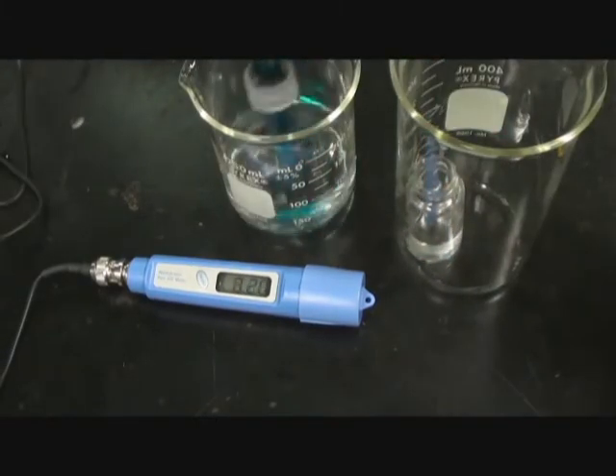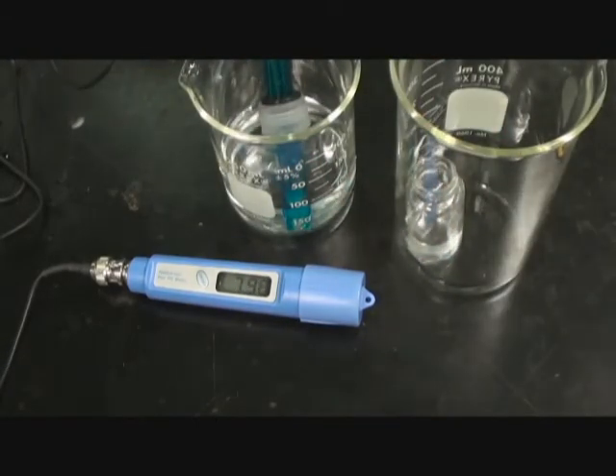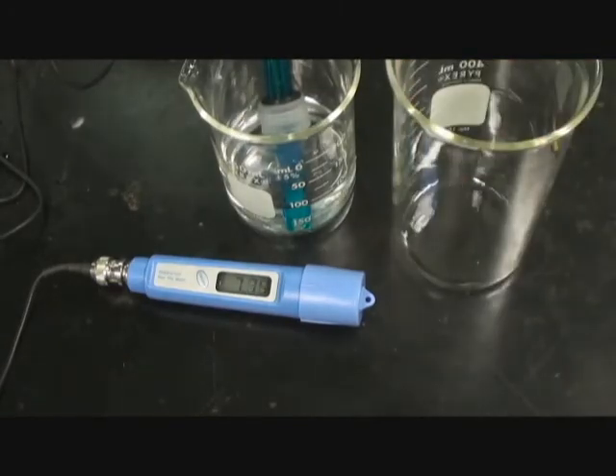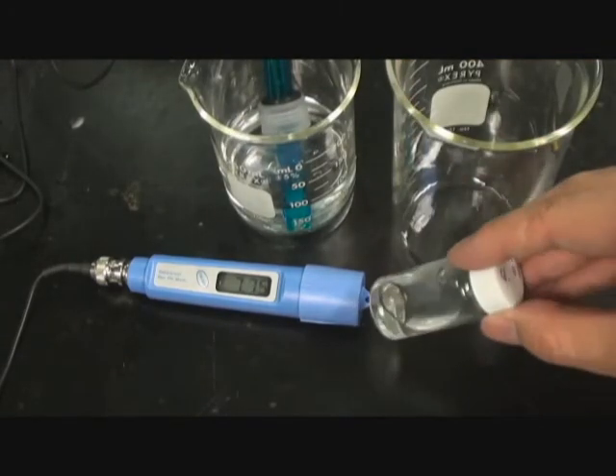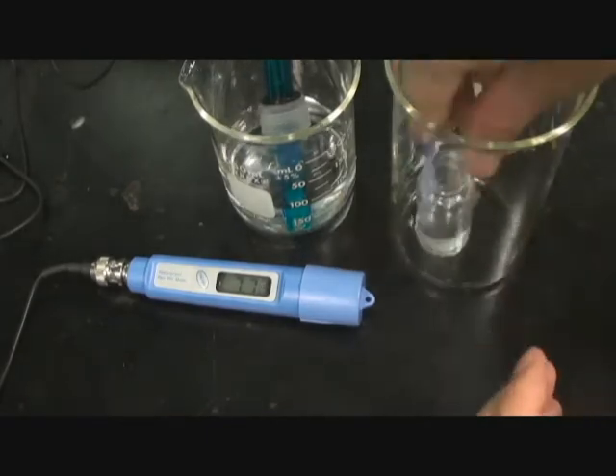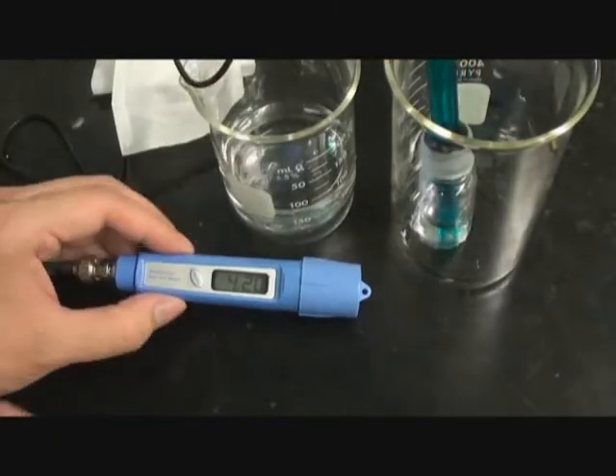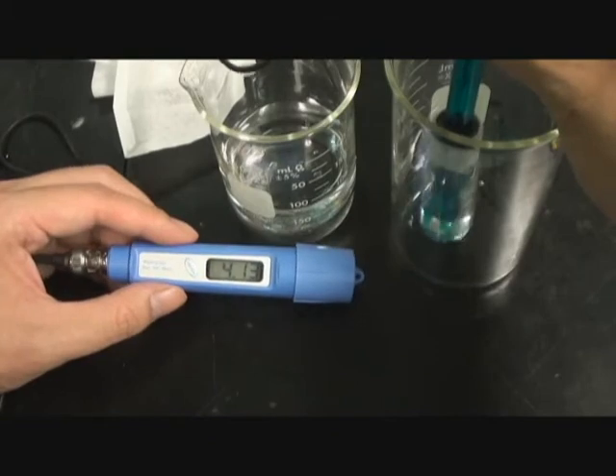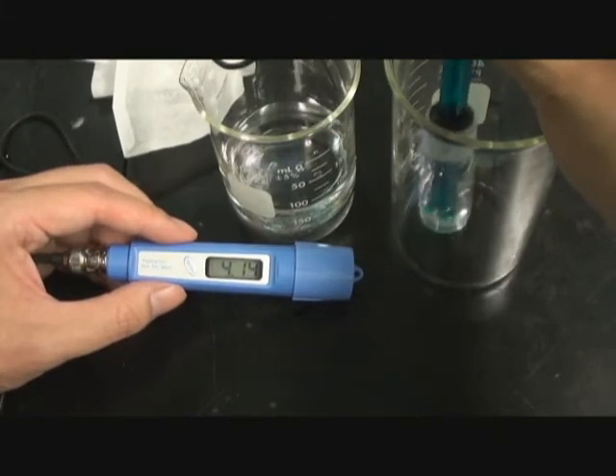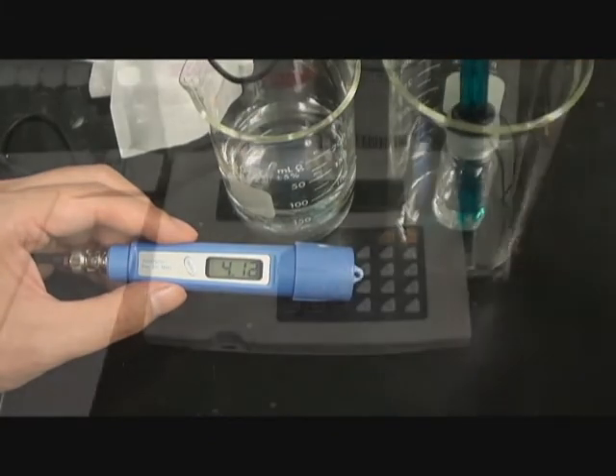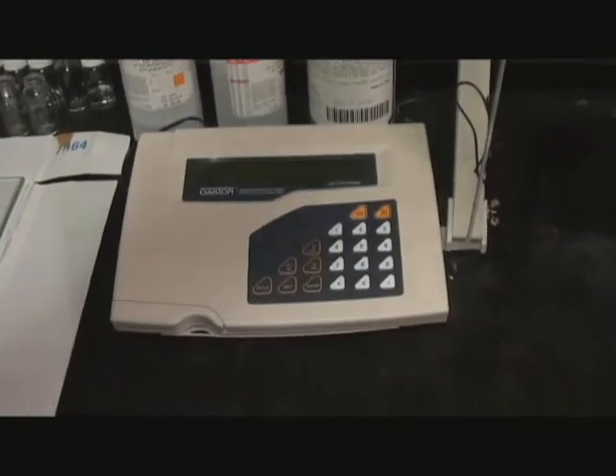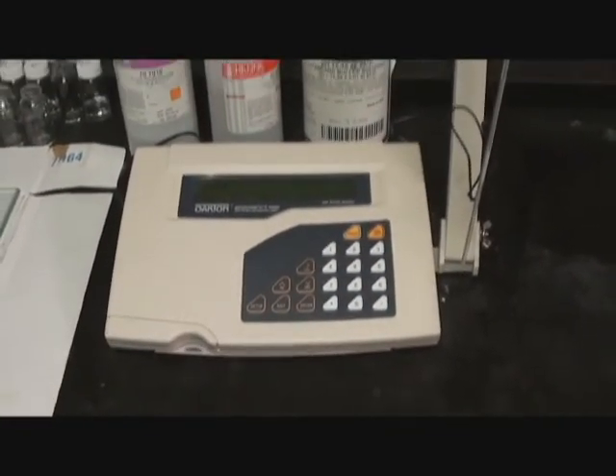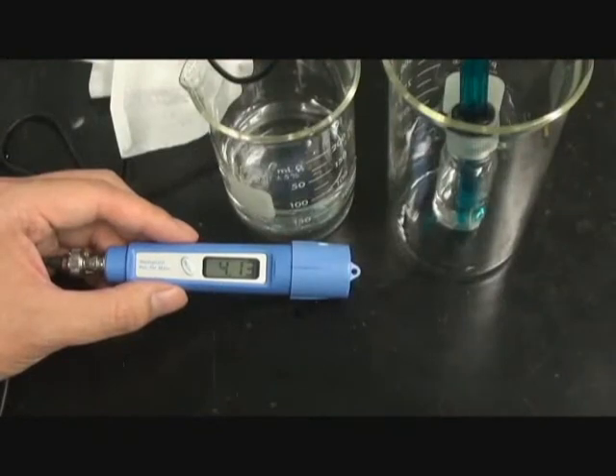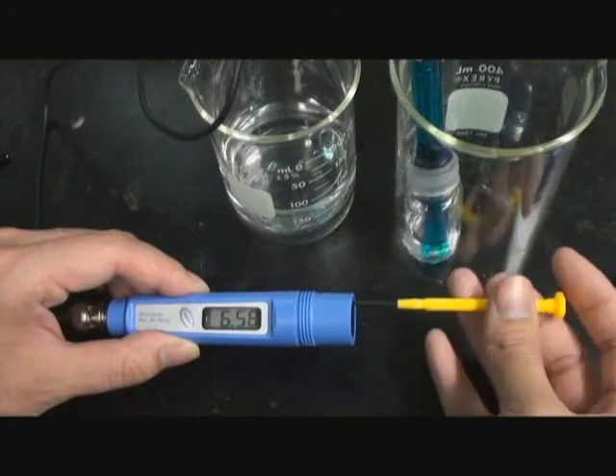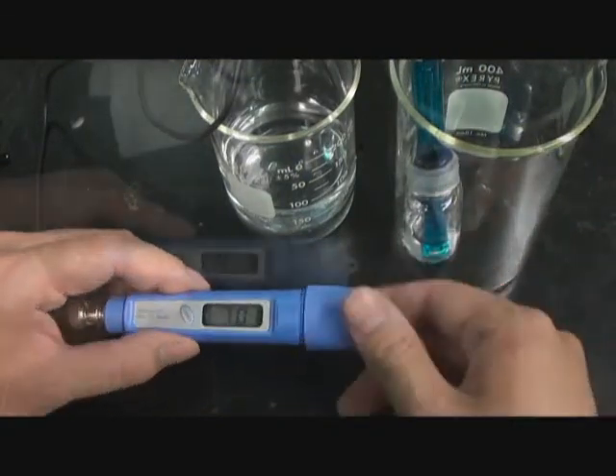What about other points? Let me get a different pH calibration solution and see if the measurement is correct. This solution has a pH of 4.01. As you can see here, the pH meter says it's off. The slope of the pH response is not correct. On a more advanced instrument, we can calibrate this new point and the onboard computer would automatically readjust the slope. But for this cheaper instrument, we don't have that kind of ability. If we readjusted this point, we would misadjust the previous point.